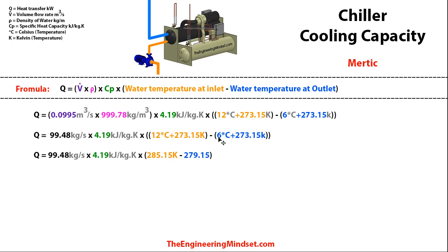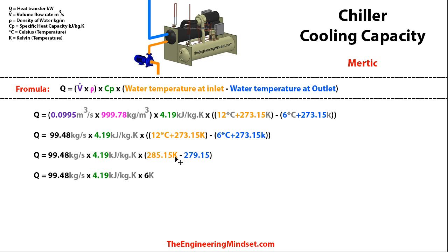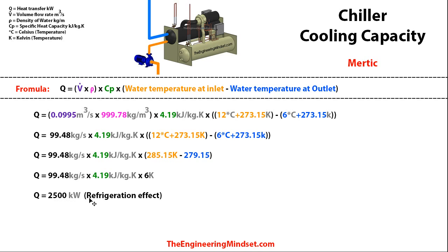Since the specific heat capacity uses per Kelvin, we convert Celsius to Kelvin by adding 273.15. So 12°C becomes 285.15 K, and 6°C becomes 279.15 K. Subtracting these gives a difference of 6 Kelvin. Multiplying all three figures together gives us 2,500 kilowatts. So this chiller, given these operating conditions, is producing 2,500 kilowatts of refrigeration.